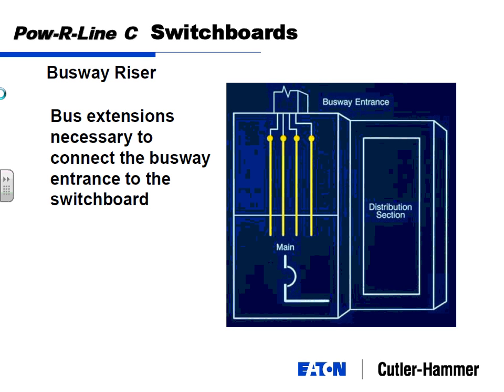Rather than cables, when you're talking 2,000 amps, you are talking about 6 cables per phase, 3 phases and a neutral, 24 cables that you've got to use a cable management system to get feeding up through raceway or through pipes, conduits, whatever you want to do. Busway takes copper bus bars, just like the horizontal bus in a switchboard, sandwiched together A, B, C, neutral. And rather than use 6 per phase for cables, you can just use one busway that might be 5 inches by 9 inches that runs from the main switchboard downstream to the 2,000 amp switchboard. And it can be very cost effective to do it that way.